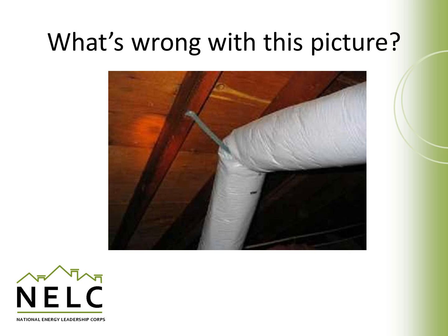Here's a good example of a common problem of ductwork in an attic that's being strapped up and pinched. This is causing some extra fan energy to be incurred and potentially also dirt and moisture to build up at the clog and the ductwork.